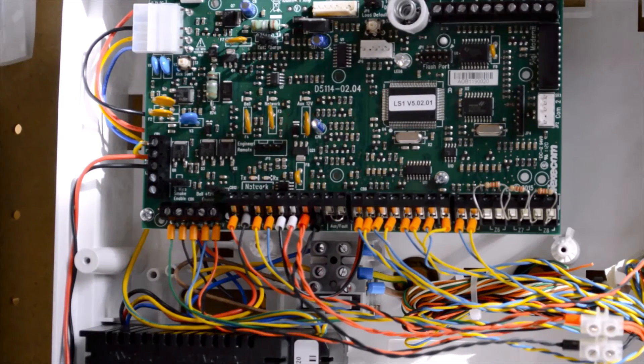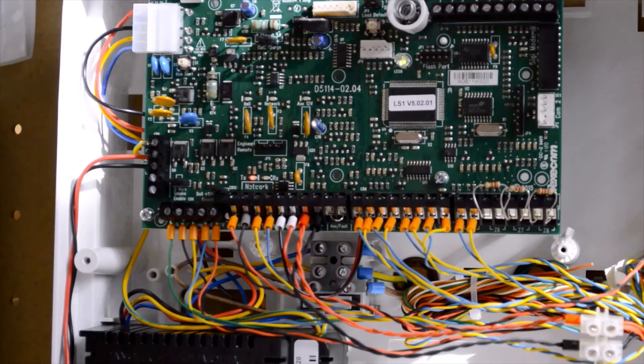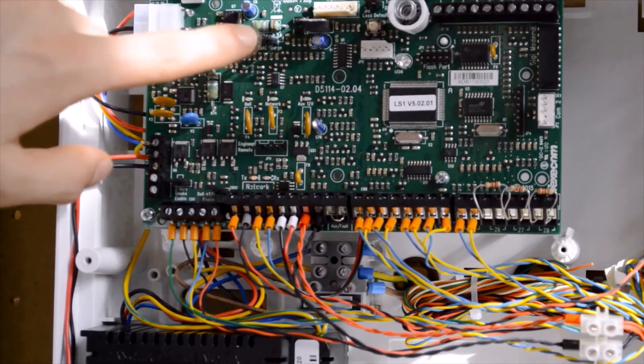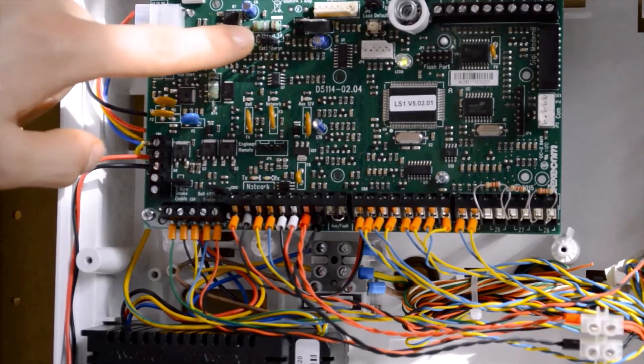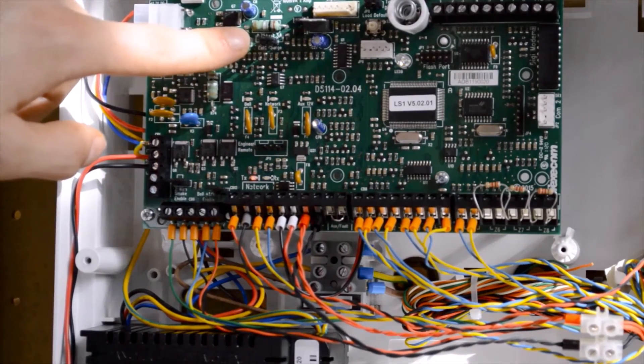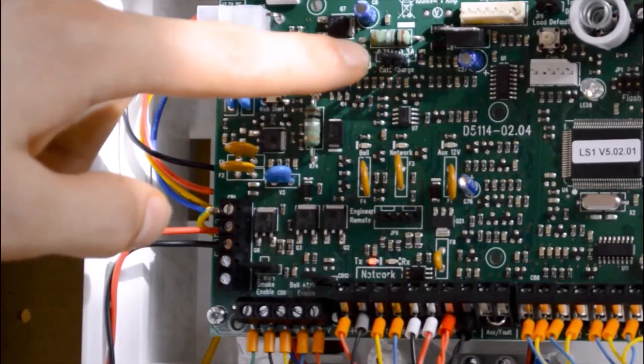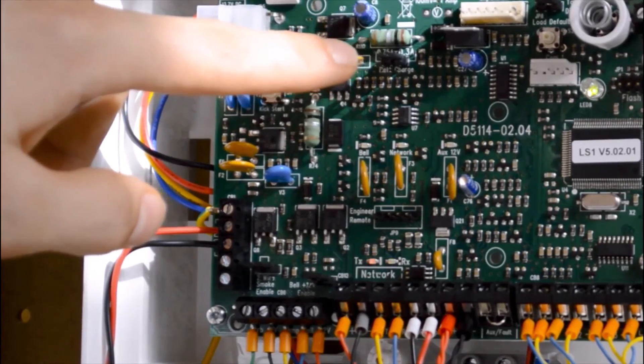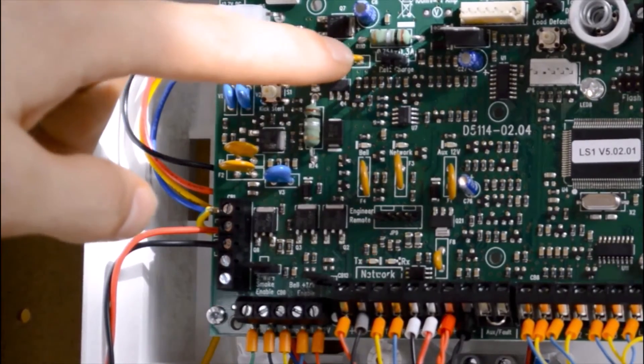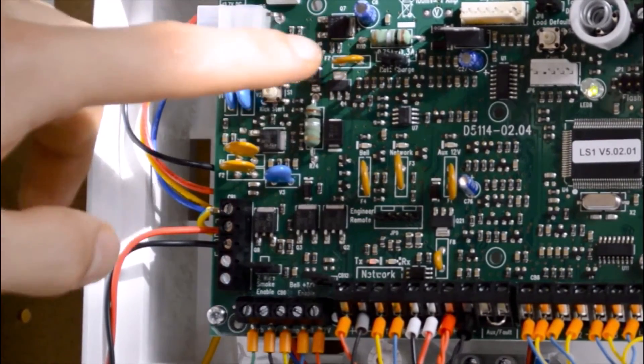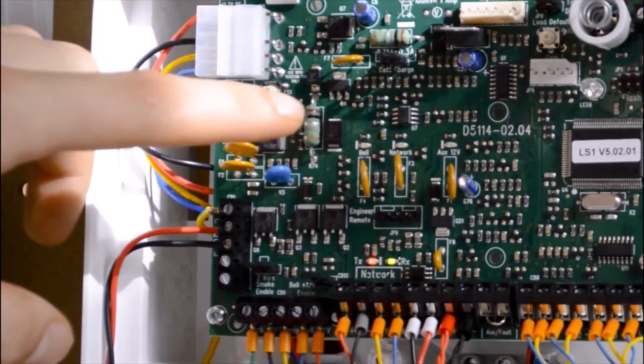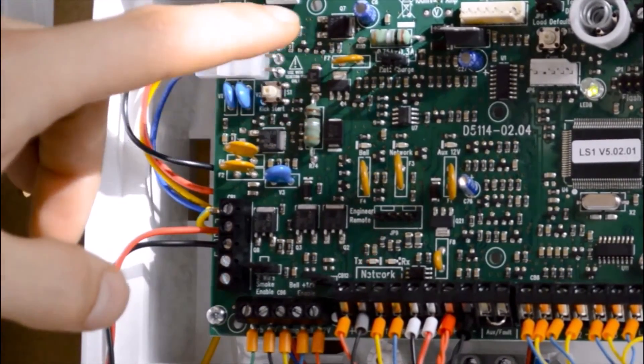The battery charge current selector here changes from 300 milliamps setting for a 7 amp hour battery to 750 milliamps for a 17 amp hour battery.